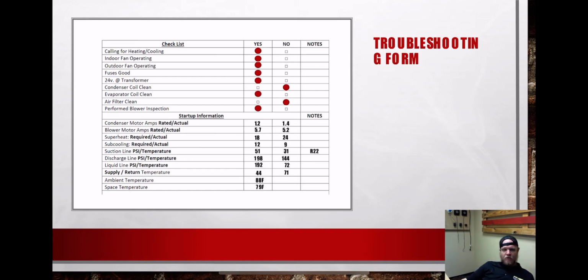So this is our troubleshooting form. This is how it should look when you guys fill it out. We'll just go right down from the top. Is it calling for heating or cooling? What does that mean? That means, is there a call? Is there 24 volts present at Y1 or Y2? And did you check it? Y1 to common, Y2 to common, W1 to common, W2 to common.